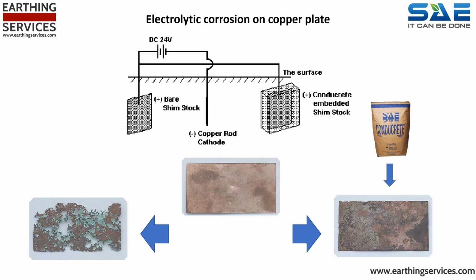Here we see aging evidence from testing which demonstrates a bare copper plate and one encased in Conducrete after repeated electrical discharges. As you can see, the bare plate has badly deteriorated. The plate encased in Conducrete only has surface scarring that occurs during the binding process. The rate of electrolytic loss is substantially slower on Conducrete than it is on bare metal, which results in a future-proofed conductor. If the bare plate had been a lattice, then there will be substantially less material present, so deterioration will be an even worse prospect.